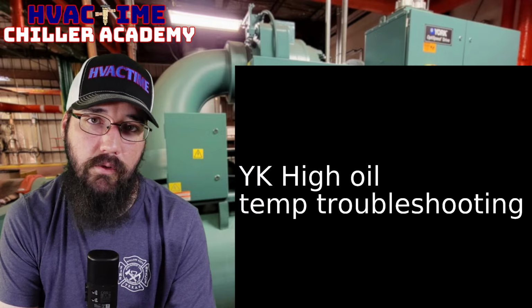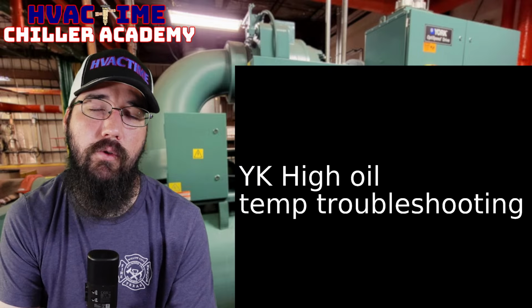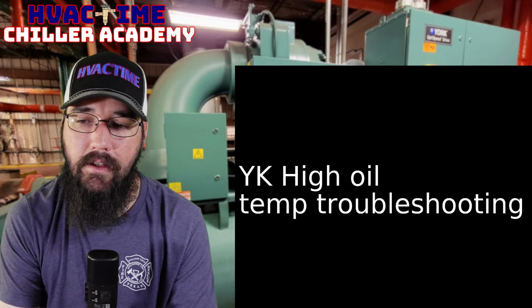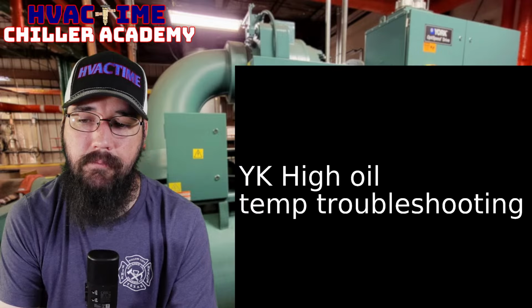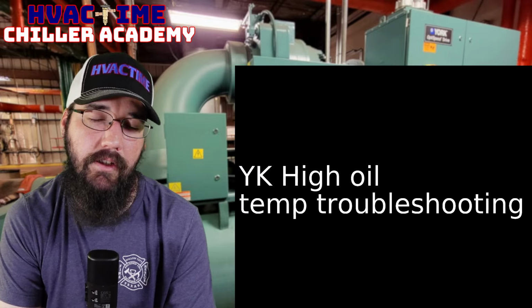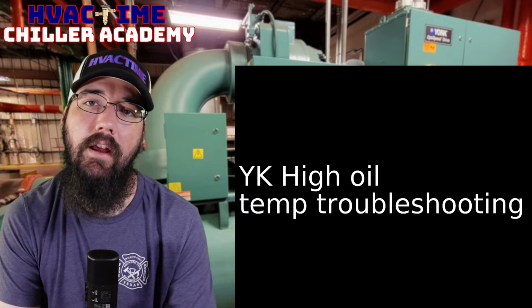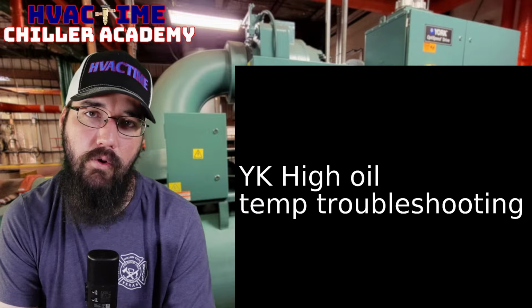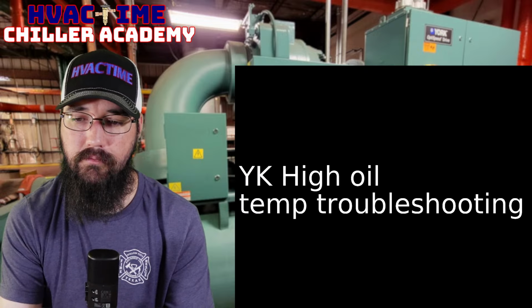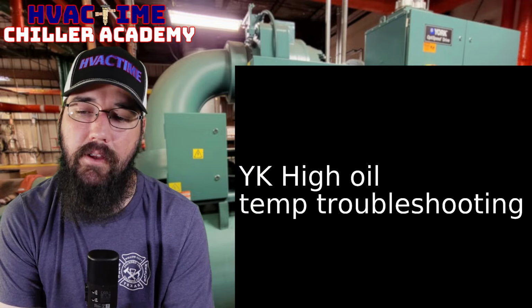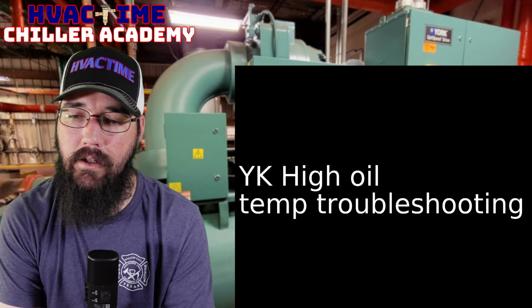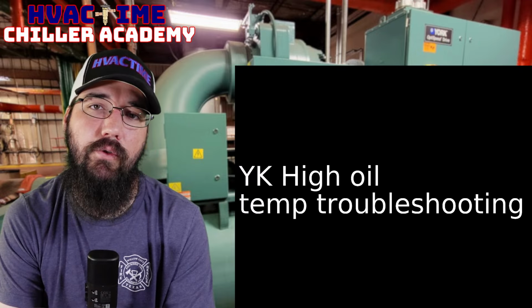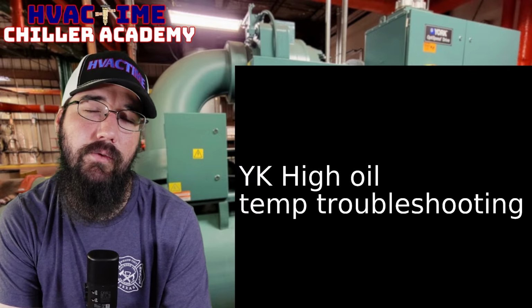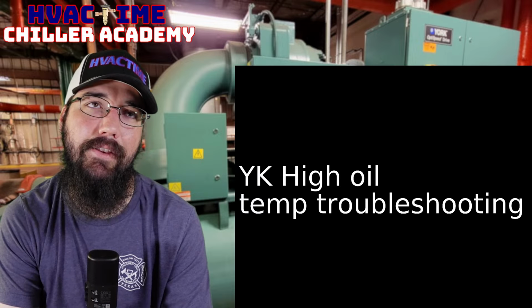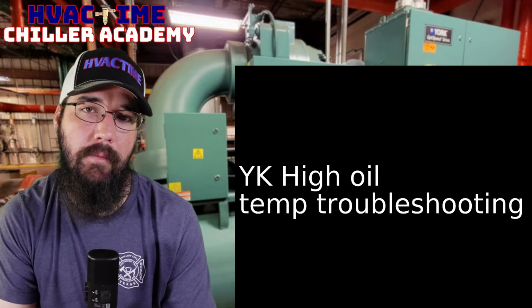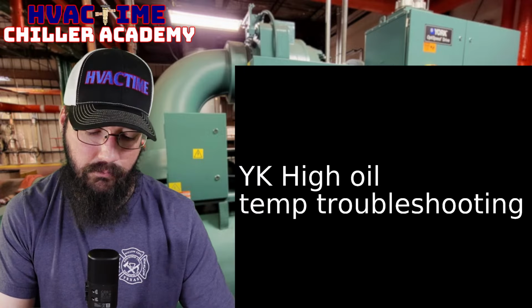It's possible that you may have enough flow to satisfy the evaporator, so you're not running into suction limiting, yet you're not giving the oil cooler enough subcooled refrigerant at load to feed enough through that cooler, right? If it came down to a condenser problem, that's the only way I could think of in the moment how high condenser water might affect it. It comes back to just what kind of subcooling we can achieve.